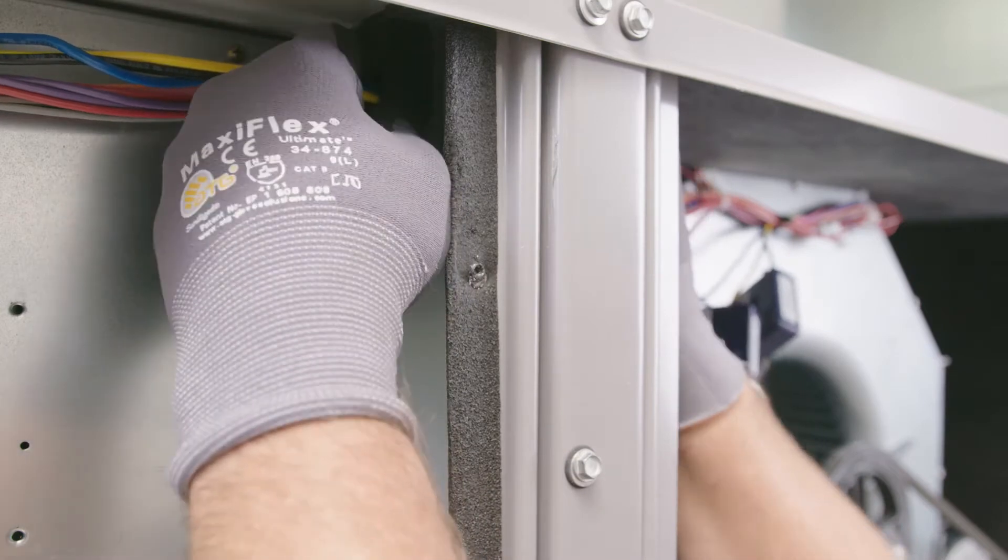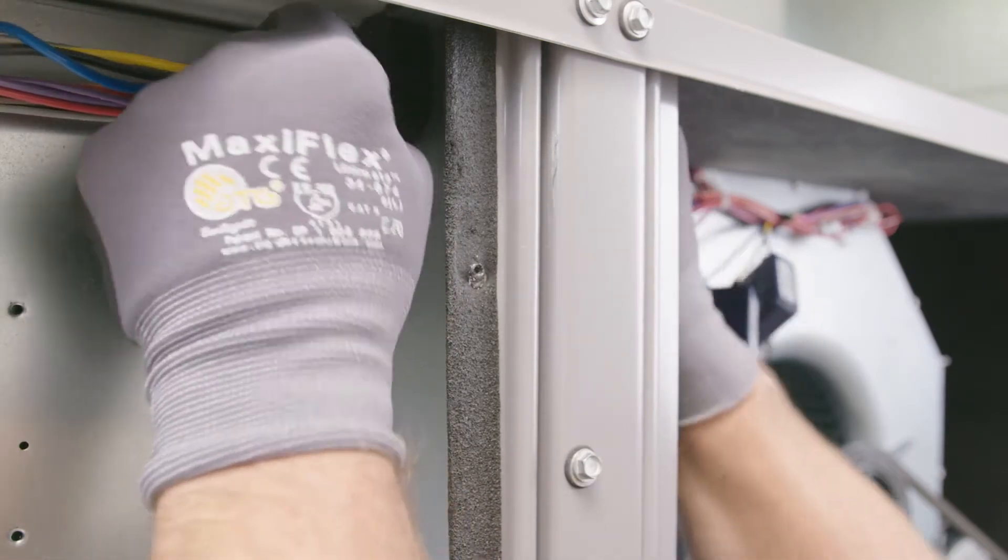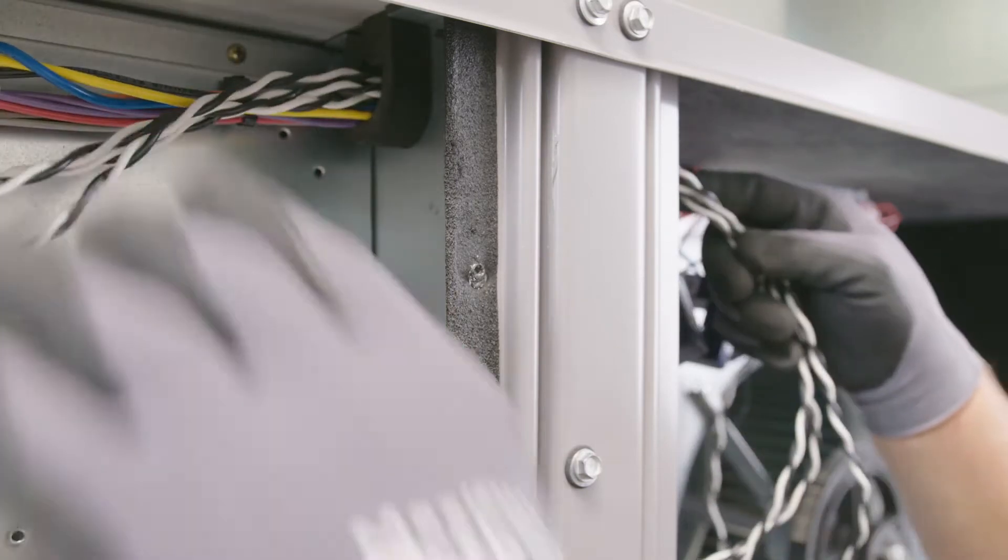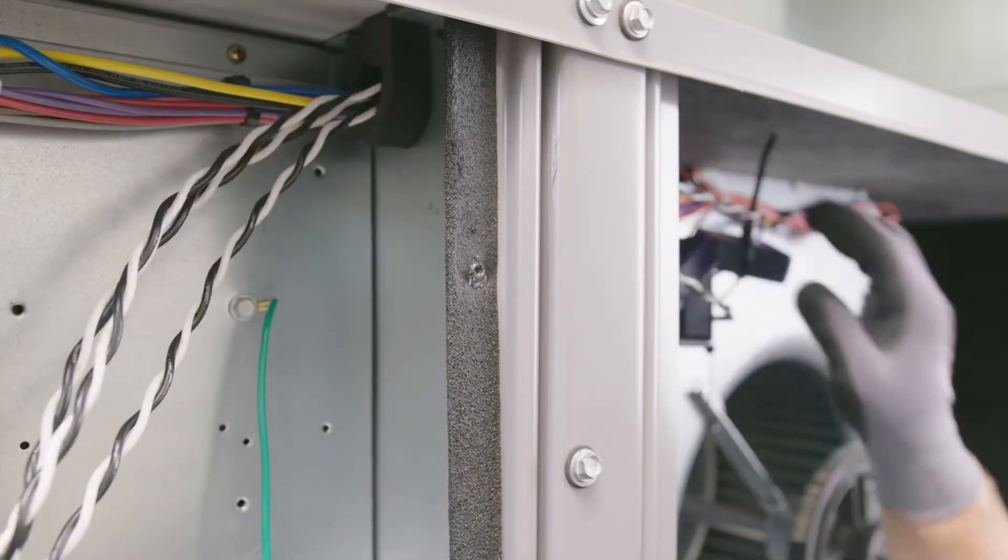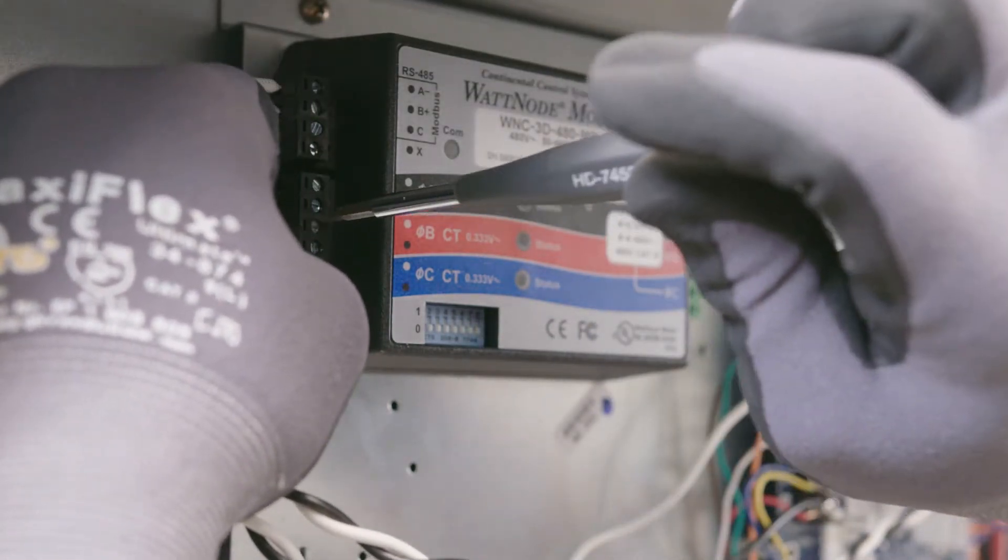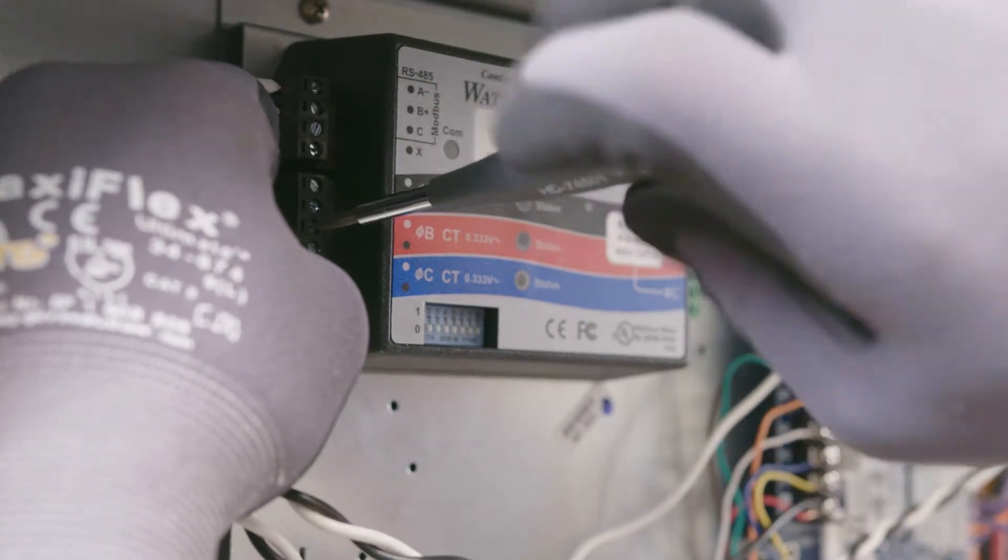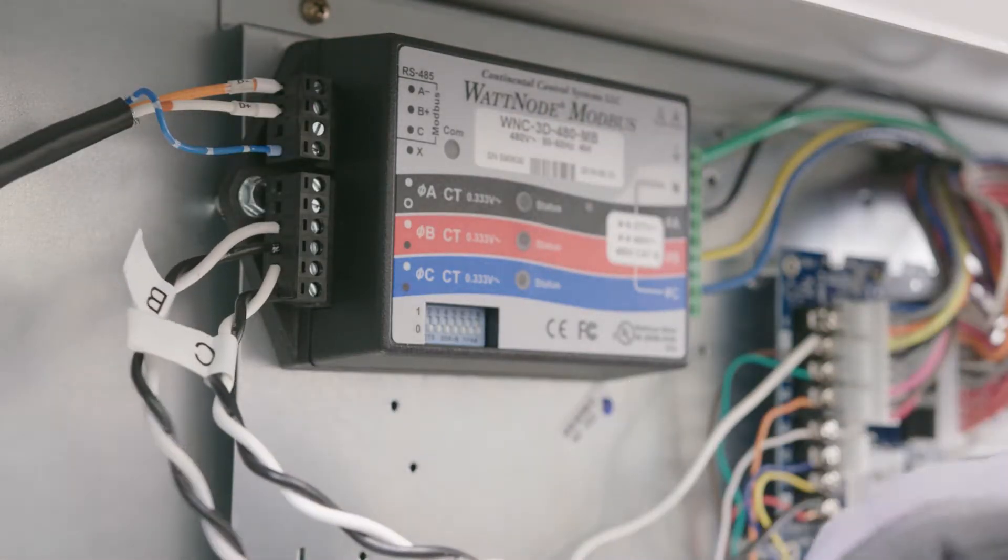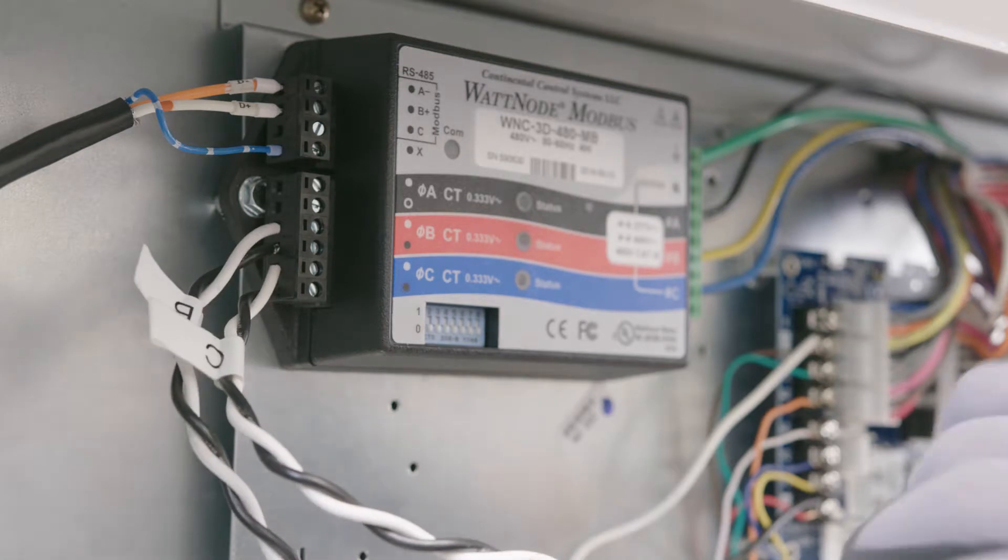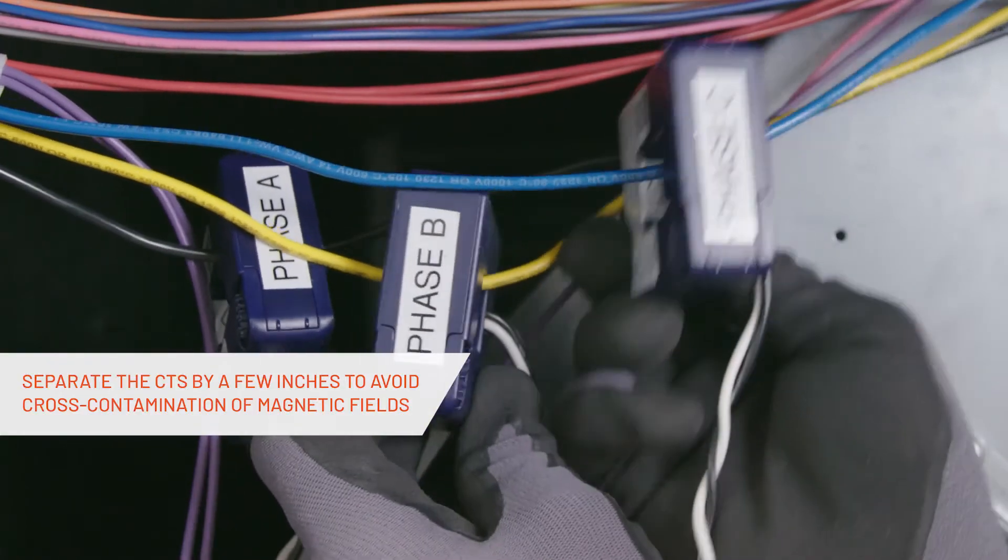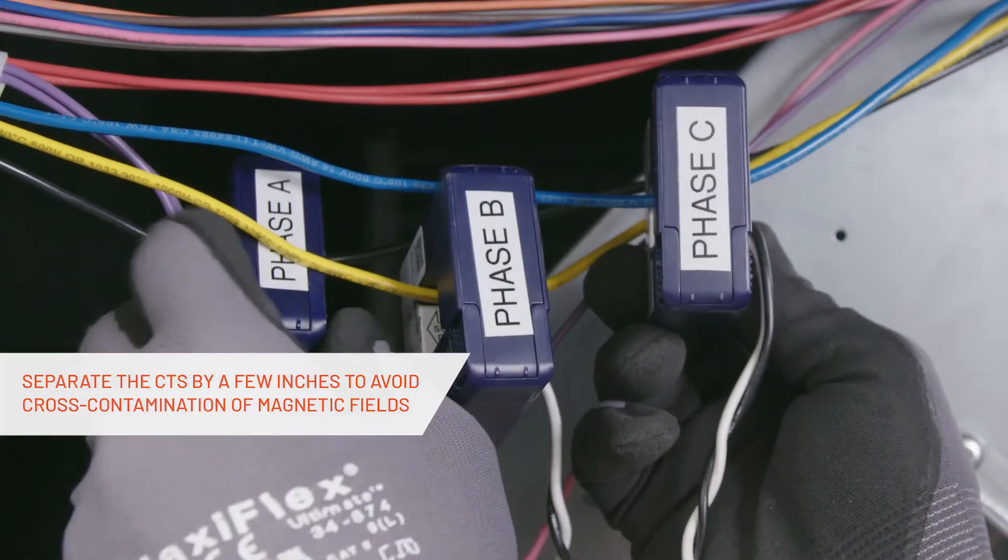The next step is to route the wires from the CTs over to the meter, which we mounted in the control panel. First, simply route the wires through the existing conduit channel for the unit. Then, mount the first A phase CT on the power wire for phase A, which is the black on this unit, again making sure the arrow on the CT is pointing towards the power source of the unit. Repeat this step with the B and C phase CTs. Make a point to separate the CTs by a few inches, so you avoid cross-contamination of magnetic fields.